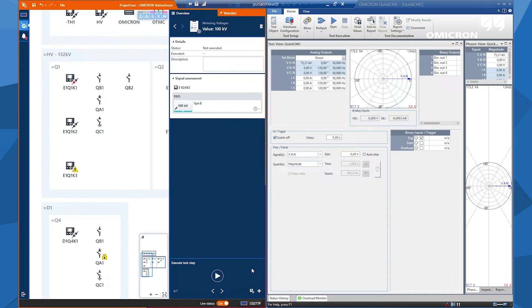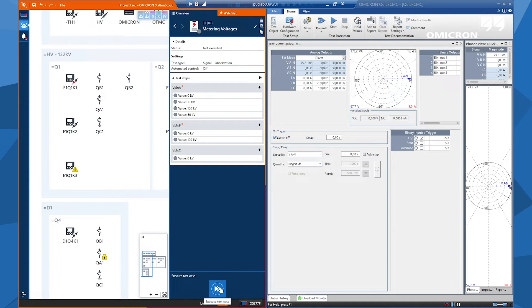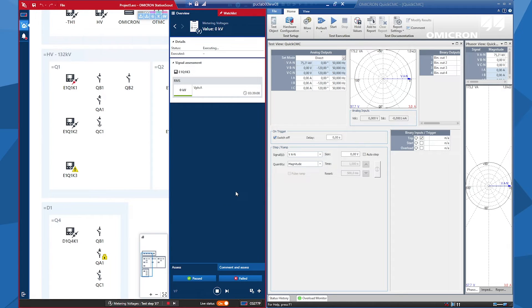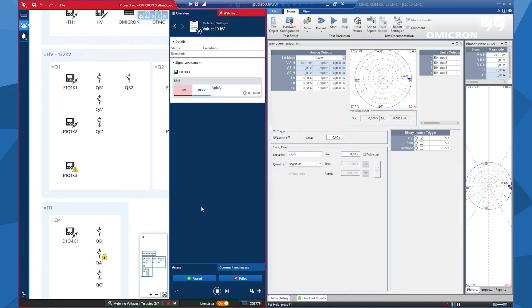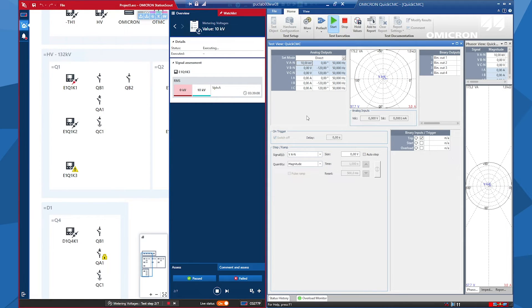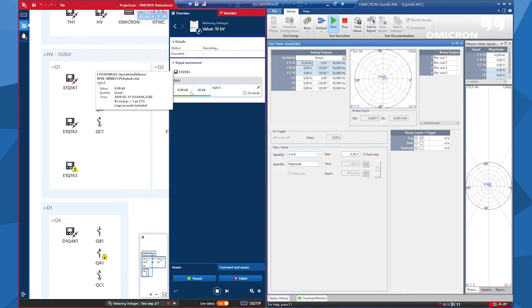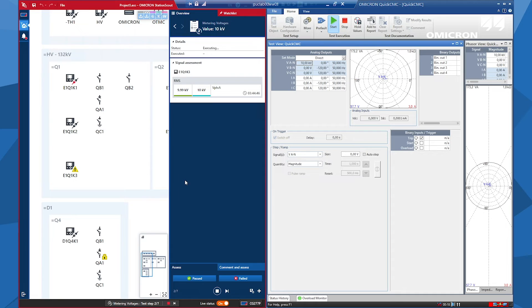Looks like we have a test plan now. We can start our test by clicking on the 'execute test case' button. On the other side of my monitor, I will inject some values from CMC. I click on 'execute test case'. Now I'm not injecting any values, so it's okay that I see 0 kV. I click past for that. And now I have to inject 10 kV via CMC — injected from phase A. You will not get exactly the same value as you inject, and StationScout has a margin of 5% here. If you are within the margin, it will be highlighted in green. We are in the margin, and this tolerance gives us a pass assessment.